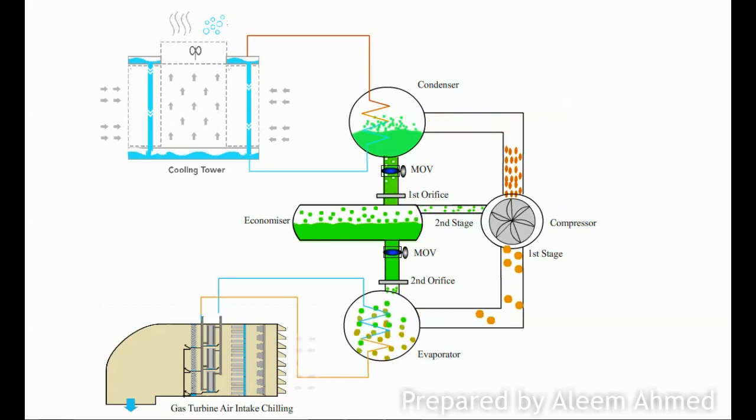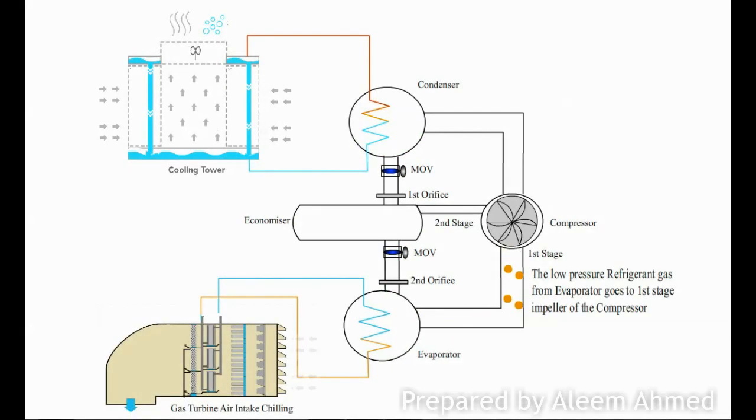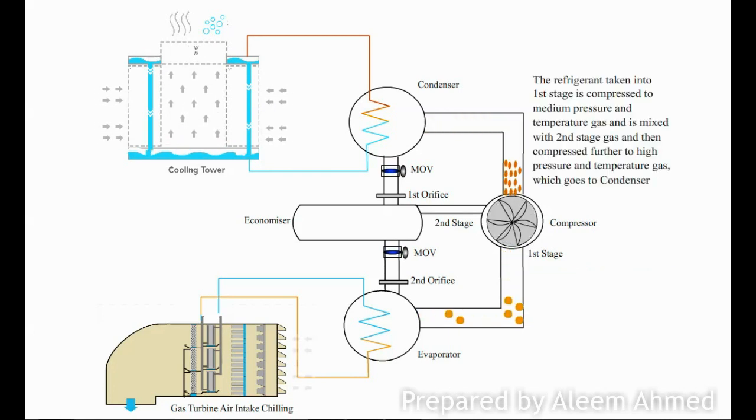Let's see step-by-step details. First, the low pressure refrigerant gas from the evaporator goes to the first stage impeller of the compressor. The compressor first stage increases the pressure and temperature to a medium range.